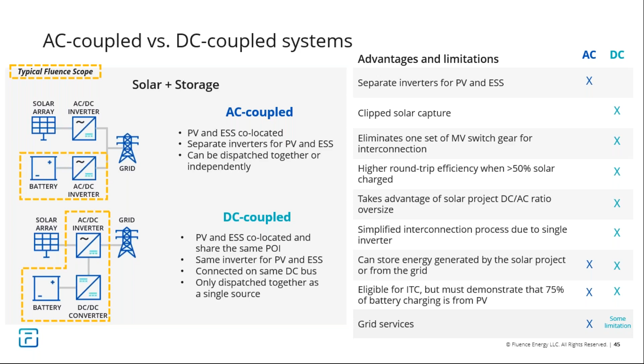One question is often around scope and how these configurations are procured. On AC coupled systems, Fluence's scope is more or less a standalone storage asset - we provide the battery and inverters, while someone else, the solar OEM, provides the solar array and solar inverter. On DC coupled systems, that's flipped around - Fluence's scope typically includes the battery, the shared inverter, and the DC-DC converters, with a third party providing the solar equipment. This creates a lot more points of interaction between the solar and battery assets for DC coupled, which can create additional challenges, so it's important to have an experienced partner.